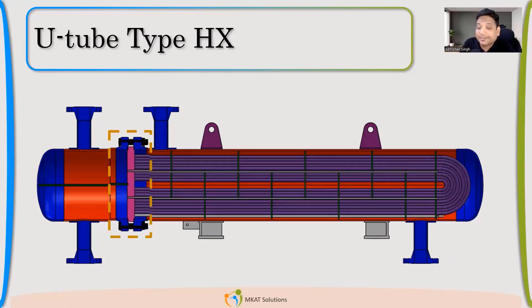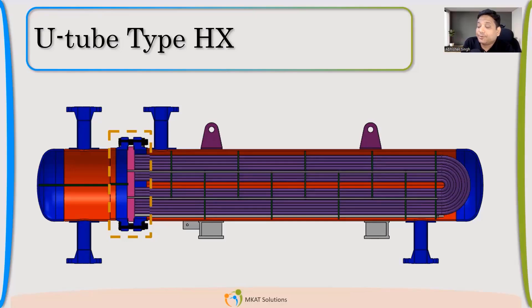Now what we are going to talk about is this: how the tube sheet is connected with the channel side and also the shell side. So in this configuration, basically your channel is having a flange, your shell is also having a flange, and your tube sheet is sandwiched. It's not integral. When it is integral, that means it is welded. The integral word in the code means welded.